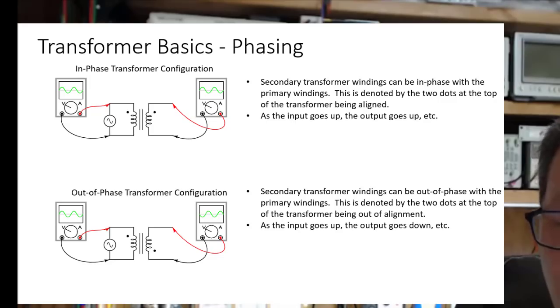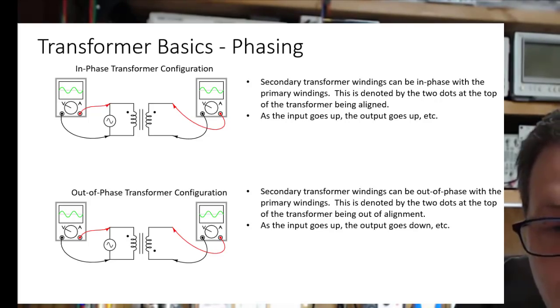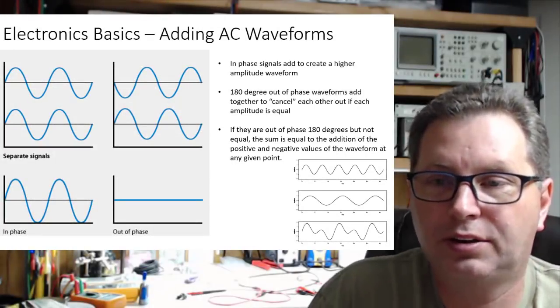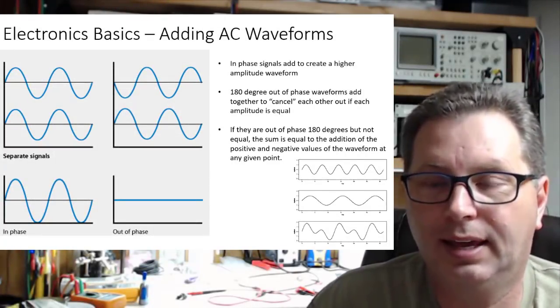That's as simple as reversing the polarity on the wires of this secondary set of windings to put it 180 degrees out of phase. That's why a lot of transformers, when marked, will show you the yellow wire is in phase with the blue wire, but if you flip it and use the white wire instead, it'd be out of phase. So transformer diagrams that come with them use these dots to show in or out of phase.